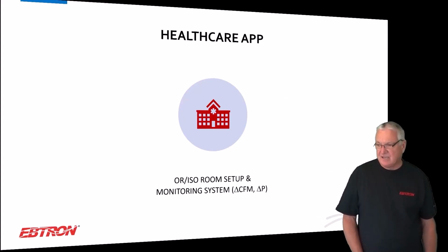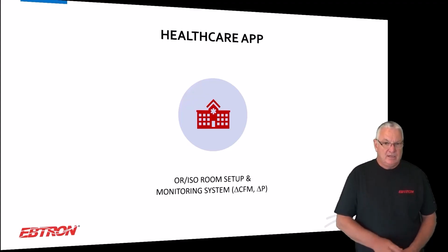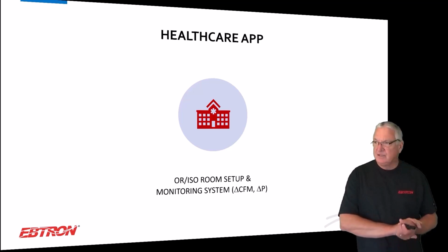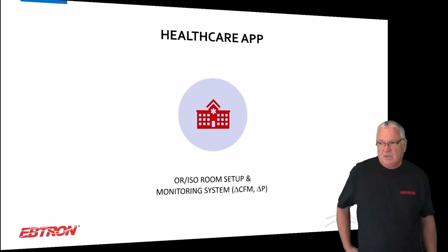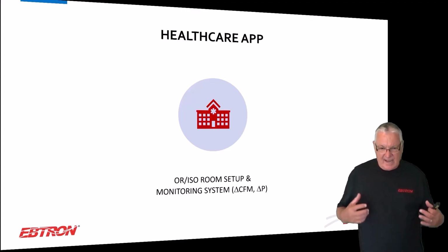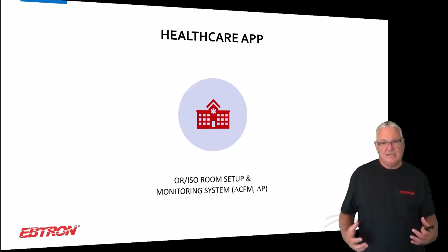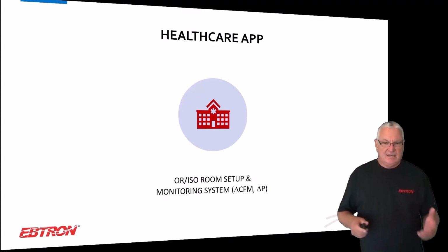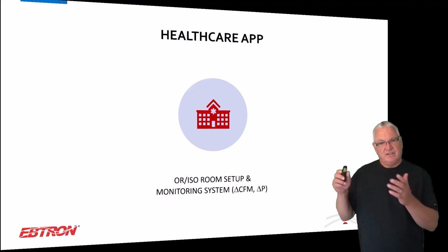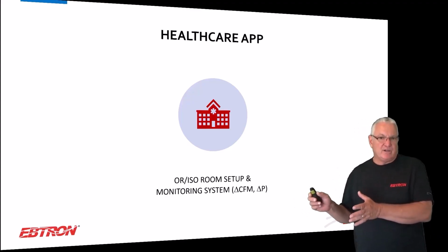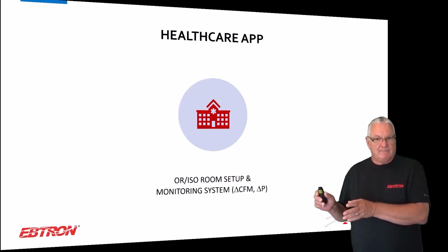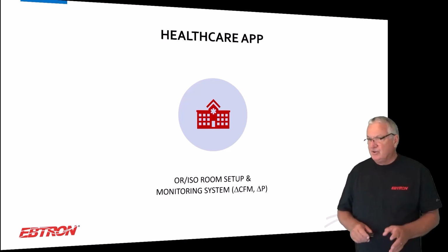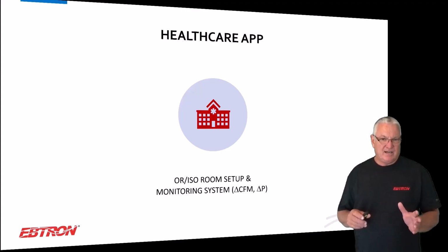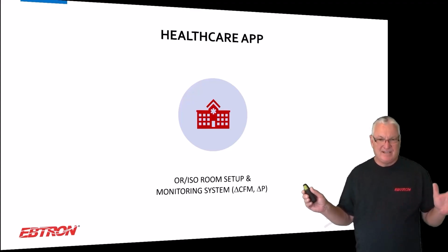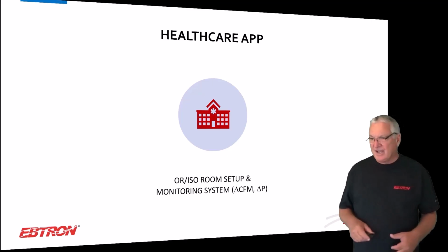The healthcare app that I think is going to be very useful for those of you that really want to get to the next level in monitoring and pressure control: basically, we're going to add a pressure sensor to the device, to the system, okay? The idea is that you use the pressure sensor to fine-tune the return. Say we're doing an OR. We have the supply flow measurement in the OR, and then we have the return flow measurement. You could try to measure those with test and balance, and you're going to be at 5 to 10%. Or you can say, hey, I located them in the right location, and it's 3%.